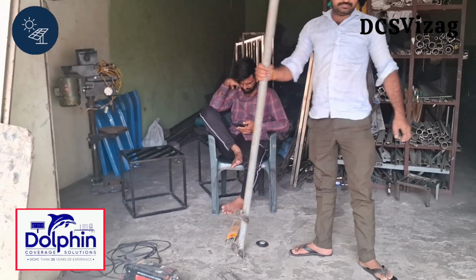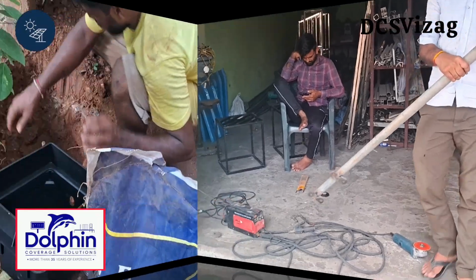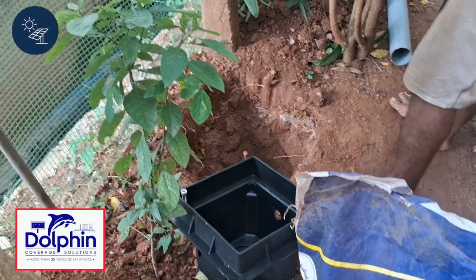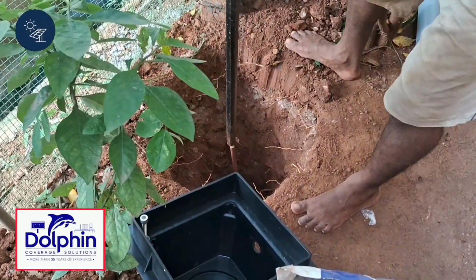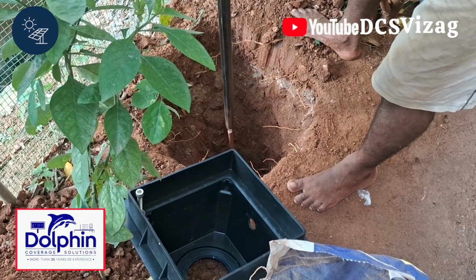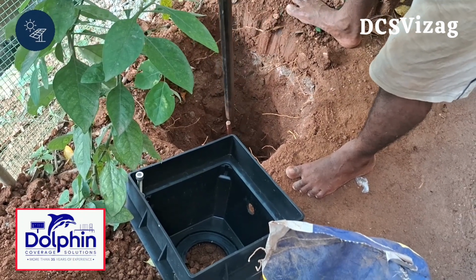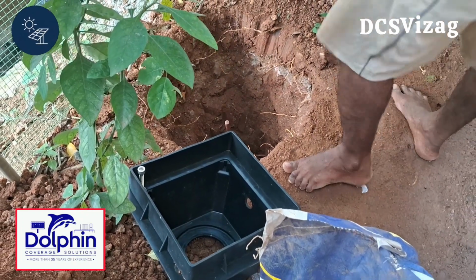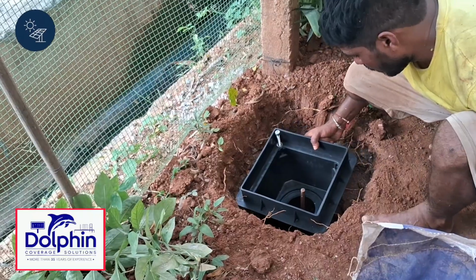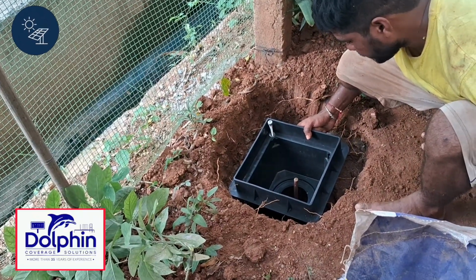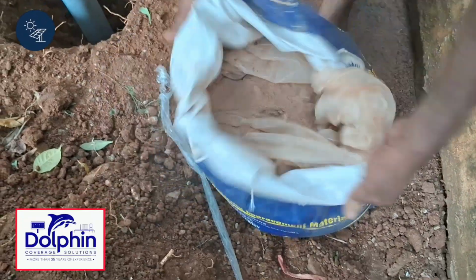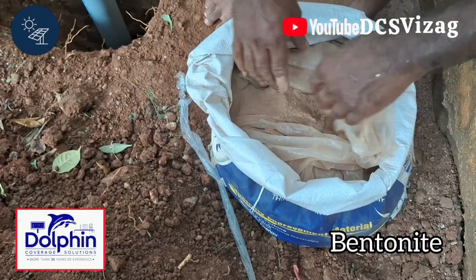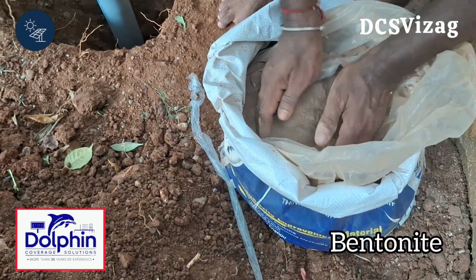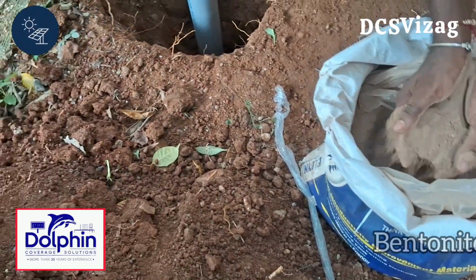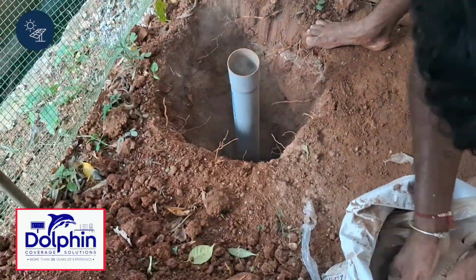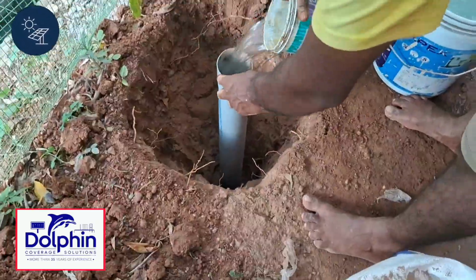Installation process. Digging the earth pit. Excavate a pit of appropriate dimensions, typically 2 to 3 meters deep for each earthing electrode. Electrode installation. Install the chosen earthing rod or plate vertically into the pit. Chemical filling, if applicable. If using chemical earthing, fill the pit with appropriate chemical compound, bentonite or BFC, charcoal, salt, around the electrode to enhance conductivity and maintain moisture.